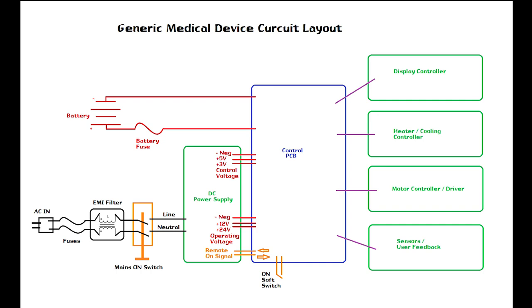Your power line coming in—it's going to have fuses someplace, an EMI filter, maybe a mains power switch, maybe not. You're going to have usually a DC power supply, which could be a part of your control PCB, you never know. And you could have an on-off switch that's a soft switch, which is basically just a signal. It doesn't actually disconnect the device from mains.